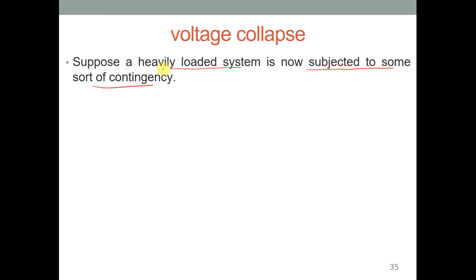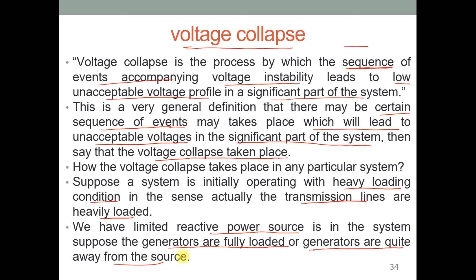So let us consider one example to understand the voltage collapse scenario. Continuing with this example, one heavily loaded transmission line is tripped. Here we have already considered the heavily loaded condition where the transmission line is heavily loaded and the generators are also fully loaded. Clear? And also we have considered that the generators are quite far from the load. So the heavily loaded transmission line is tripped, and the moment this happens, the other lines will be further loaded. That means the power transferred by the tripped line is distributed to the other transmission lines, and that's why the other lines will be further loaded, the reactive power consumed by these transmission lines will increase, and this will cause a reduction in voltage. Of course, recall the transmission system characteristic: if a fault occurs, or if the load increases, then the reactive power demand of the system increases, and the voltage at that particular bus or generator decreases.